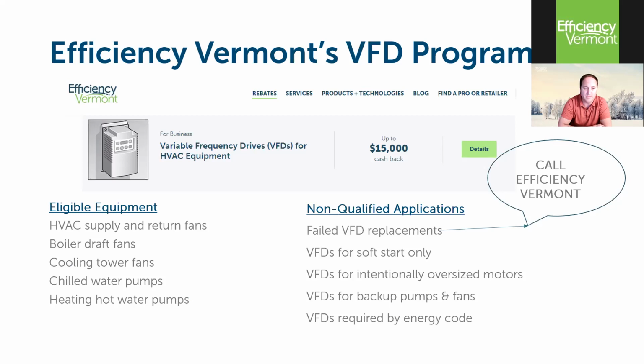And like I said, there's not many. I don't think I've ever seen a 100 horsepower HVAC pump or fan in Vermont, but maybe they exist. Point being is this is an easy process. If you put a drive in on a qualified end use application, one of these applications on the left side, it is literally an electronic process, not dissimilar from getting a rebate from lots of different things. Upload your invoice as long as it clearly states the VFD model number and manufacturer, as well as the end use, which is part of the application. It's a very easy process.